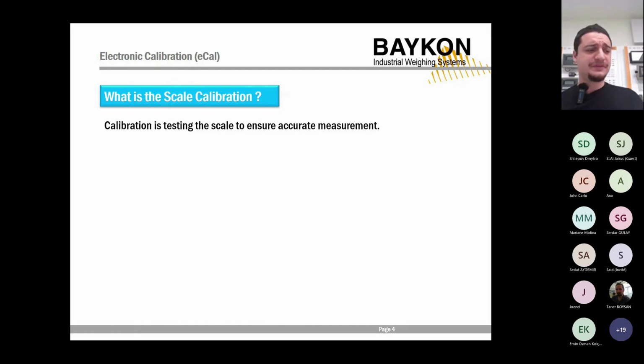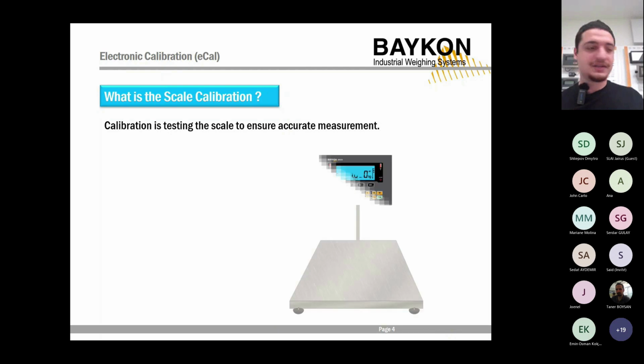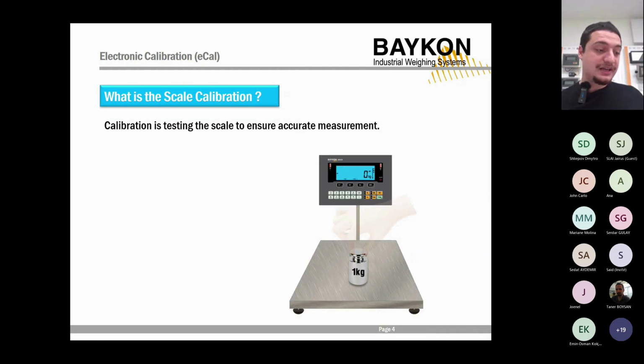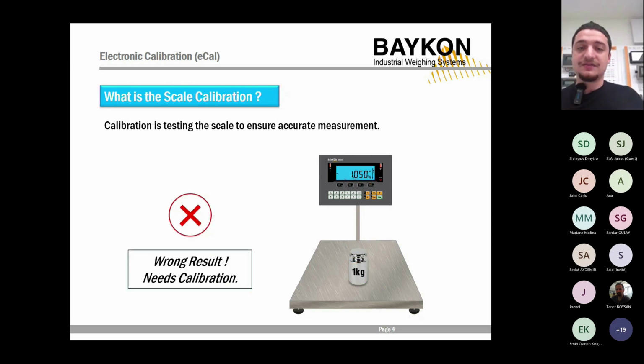So what is scale calibration? Calibration in the weighing industry, in its simplest definition, is ensuring whether a measuring equipment is testing accurately or not. As simple as that. We have a scale. You can see it on the slide. And as you can see, the scale that we have on the slide is weighing the test weight placed on it incorrectly. In other words, the scale needs to learn the amount of weight placed on it. And calibration is basically teaching the scale the amount of weight it has on its current state.